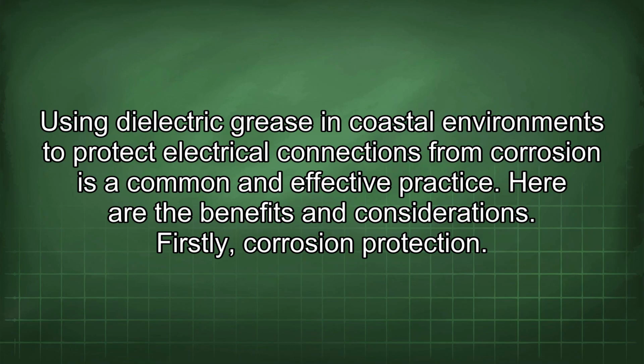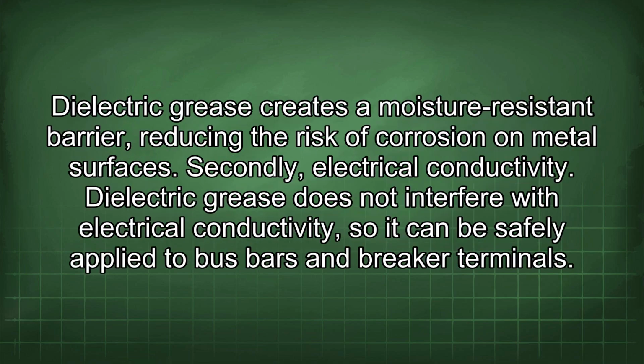Using dielectric grease in coastal environments to protect electrical connections from corrosion is a common and effective practice. Here are the benefits and considerations. Firstly, corrosion protection. Dielectric grease creates a moisture-resistant barrier, reducing the risk of corrosion on metal surfaces.